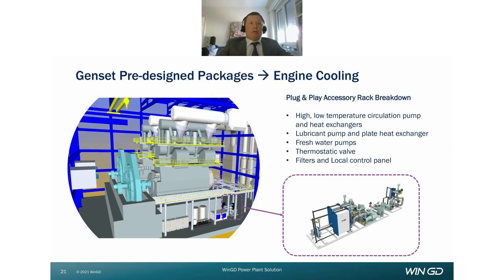Back to the mechanical modules. Let's look in more detail at the engine cooling auxiliaries. They are hosted in a module named Accessory Rack. This module has been designed to integrate the engine pumps dedicated to the low and high coolant temperature circuit, along with the respective thermostatic valve, filters, etc. In particular, the module depicted here is designed for sea or freshwater open loop cooling. A closed loop cooling system adopting a dry cooler is also available.